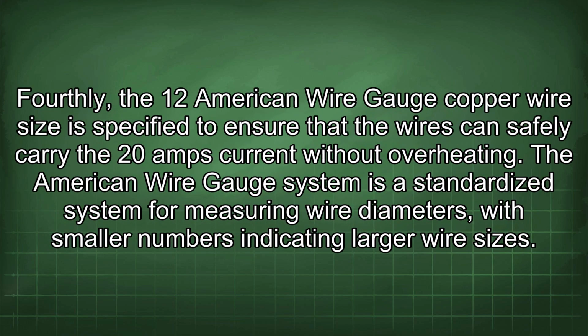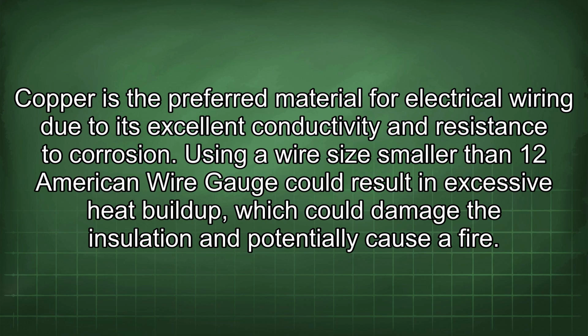Fourthly, the 12 American wire gauge copper wire size is specified to ensure that the wires can safely carry the 20 amps current without overheating. The American wire gauge system is a standardized system for measuring wire diameters, with smaller numbers indicating larger wire sizes. Copper is the preferred material for electrical wiring due to its excellent conductivity and resistance to corrosion. Using a wire size smaller than 12 American wire gauge could result in excessive heat buildup, which could damage the insulation and potentially cause a fire.